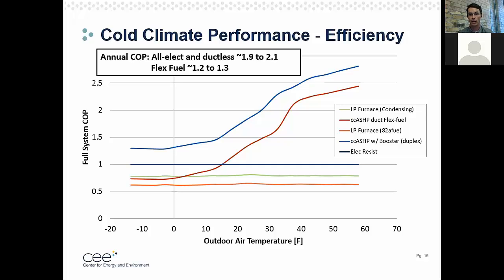So what that resulted in from an efficiency level over the winter was your all-electric and ductless systems are producing around 1.9 to 2.1 is your average COP over the entire winter season. That means that they're operating at 200% efficiency compared to electric resistance because they're moving that heat around. They're able to get those extra benefits and deliver a ton of efficiency and savings. With your flex fuel system, it's a little bit lower because of that hard switchover. So the average COP over the winter when we tested was 1.2 to 1.3. You're still getting over 100% efficiency with those systems. It's just a little bit lower with that switchover.